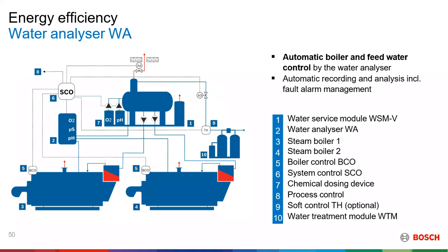So this is only for monitoring purposes. And in this setup, you will have the same system control with probes around the boilers and together with the feed water tank. Then, as you can see, there are two chemical treatment plants next to the feed water tank for O2 and pH correction. So here, the system control will monitor the different parameters of the water at the different points, and it will be able to control the amount of O2 scavenger and pH correction chemical that you're using in your boiler.